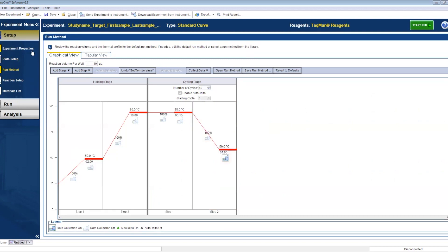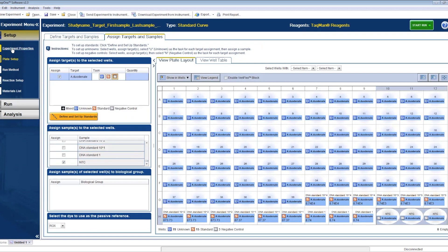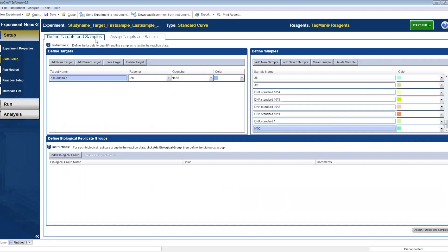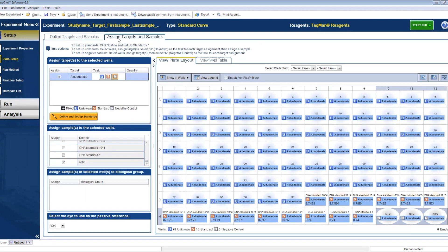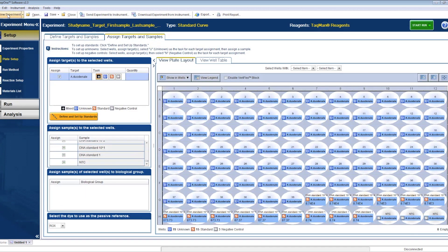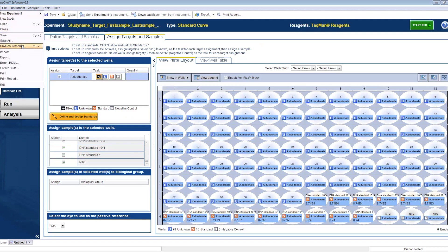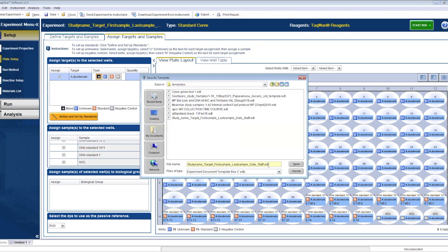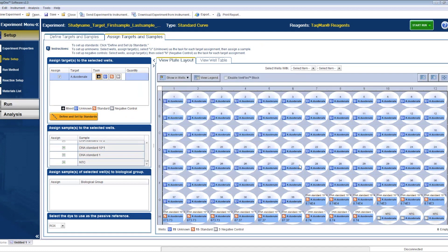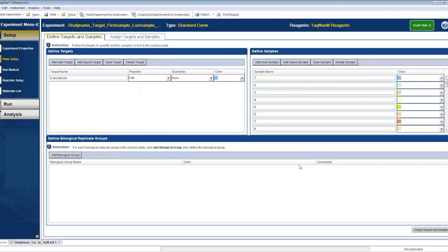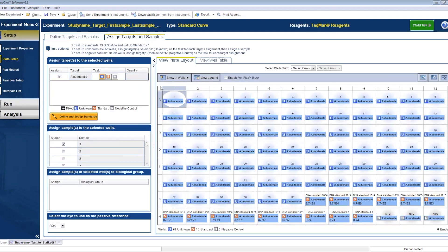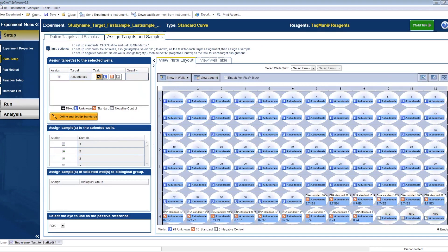Then go back to your screen and you can save this whole setup as a template or .edt file. Next time you're running the same samples, you can use the saved template, but do not forget to change the name of the run, the target, and specifications regarding the copy numbers in the standards if needed. The machine will not let you run the plate unless you save your run. Press run and that's it!